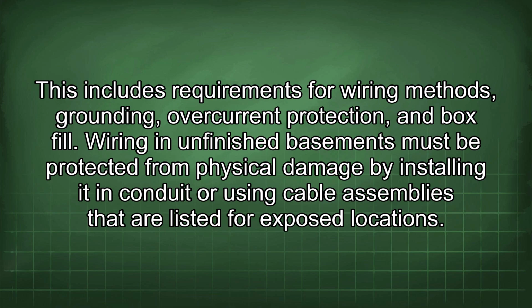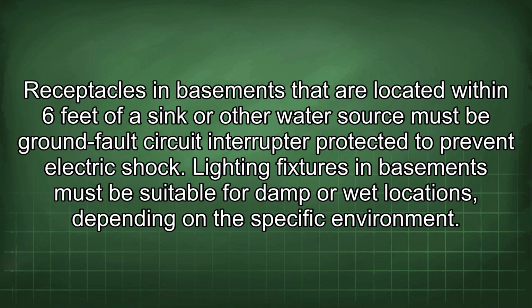Wiring in unfinished basements must be protected from physical damage by installing it in conduit or using cable assemblies that are listed for exposed locations. Receptacles in basements that are located within 6 feet of a sink or other water source must be ground fault circuit interrupter protected to prevent electric shock. Lighting fixtures in basements must be suitable for damp or wet locations, depending on the specific environment.